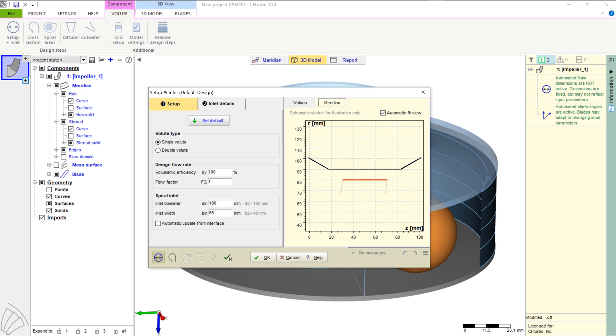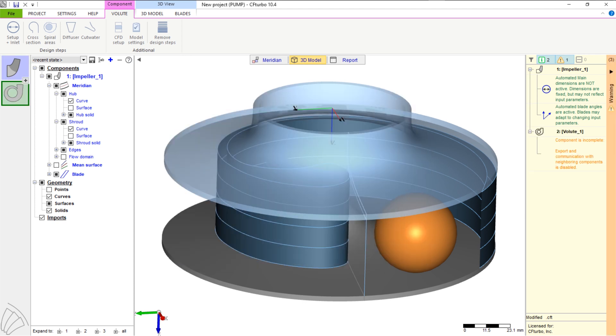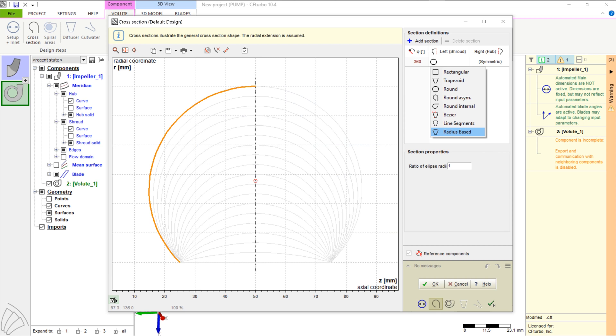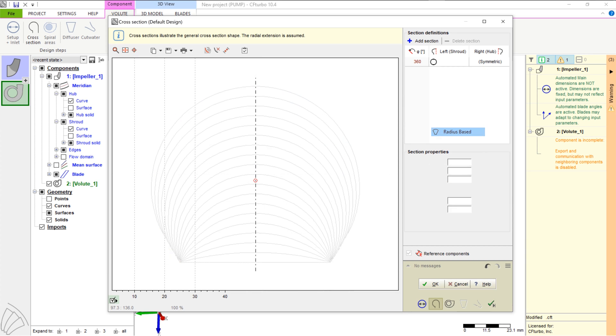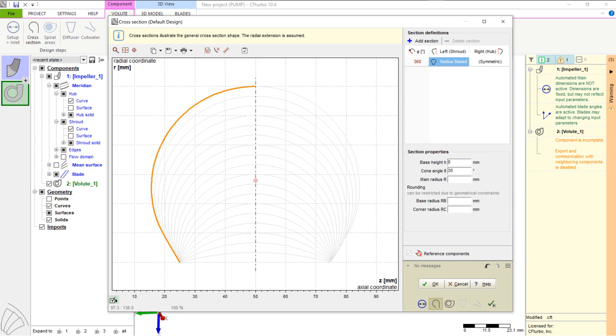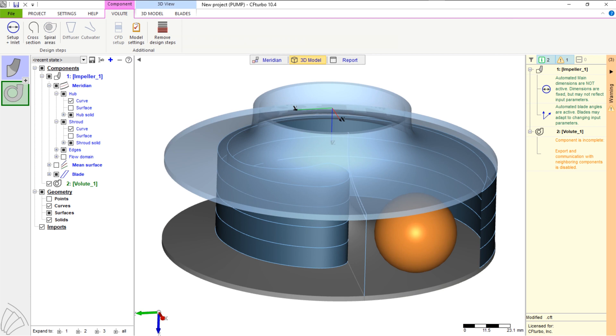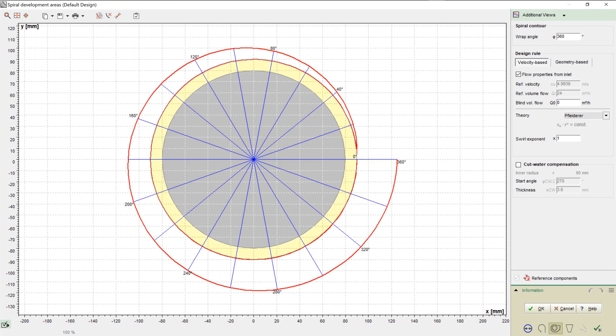Now we create the next component, which is the volute. For volute design, we can select different cross sections like round, radius based, freeform, etc., all symmetric and asymmetric. The cross section shape can vary in circumferential direction as well. There are different velocity based design rules to calculate the extension of the spiral. For example, the user can select between Pfleiderer or Stepanoff equations.